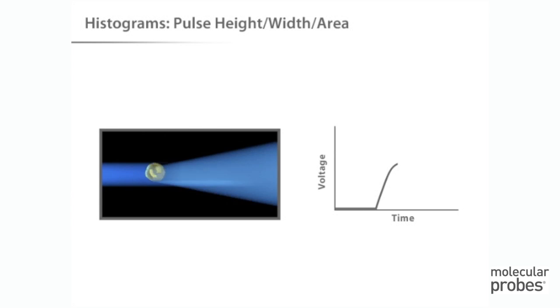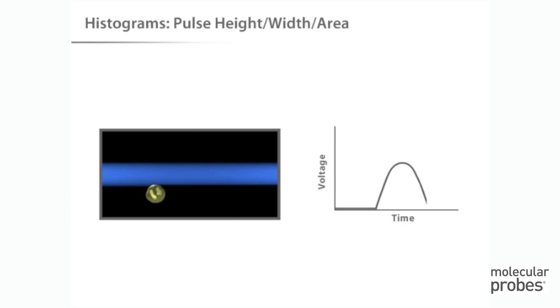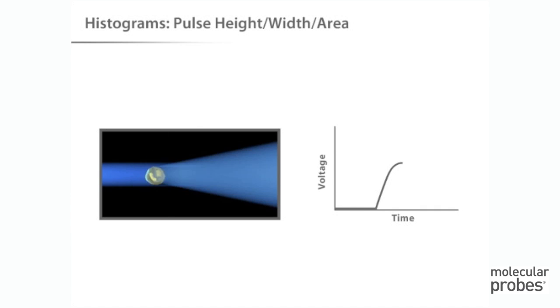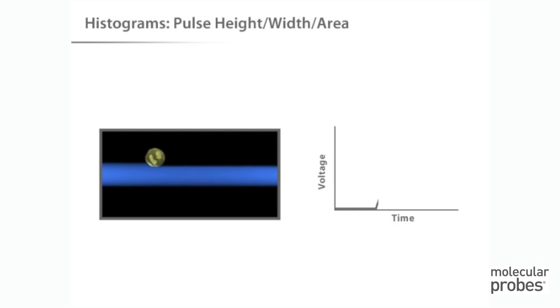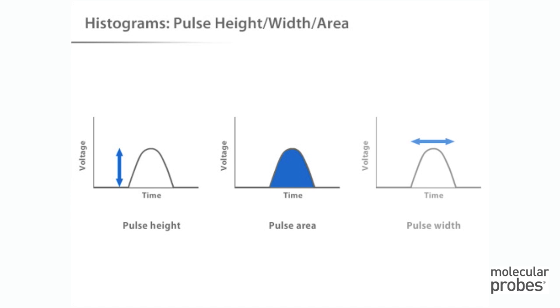Let's take a look at data collection. As a cell passes through the laser beam in the flow cytometer, it sends a light pulse to scatter and fluorescence detectors. That light is converted into a voltage pulse. In order for this pulse to be useful for analysis, it must be converted into a numerical value, and this can be done in any of three ways: the height of the pulse can be measured, the area under the pulse can be measured, or the width of the pulse can be measured.